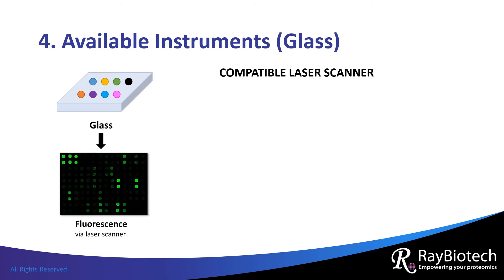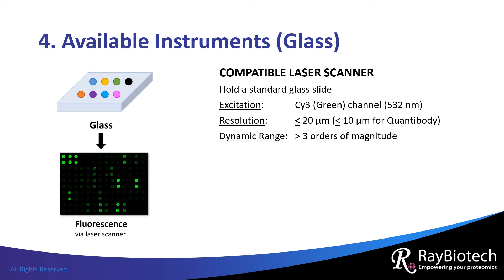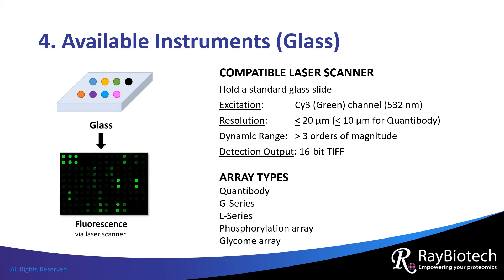If you want to process the arrays yourself, which instruments can you access? For glass slides, you will need a compatible laser scanner. The scanner should be able to hold a standard glass slide, detect Cy3 fluorescence, have a resolution of at least 20 microns, have a dynamic range of at least three orders of magnitude, and create a TIFF image of the scan. Antibody arrays with a glass substrate include Quantibody, G series, L series, phosphorylation array, and glycome array.